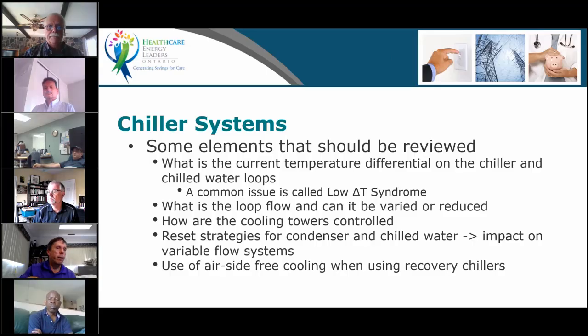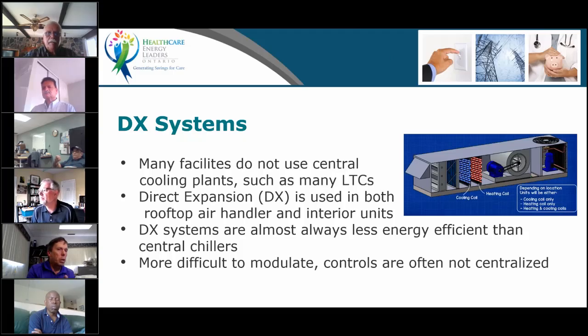And that's why if you look at some of the standards, such as ASHRAE 90.1, they do not require reset strategies on chilled water when it's variable flow because of the impact it may have on pump power. It doesn't mean not to look at it, but just to be careful when you look at that. You will also have DX systems in the smaller systems. And some of the measures we discussed previously, such as reducing or cutting the airflow to some zone, may provide problems for those systems. If you have a DX system with a gas heating coil, and you reduce the flow capacity, well, depending on the number of stages of cooling, you may run into issues.